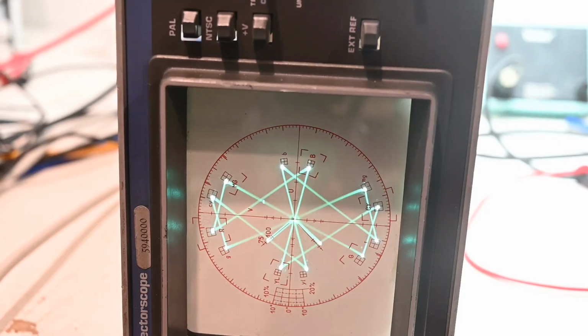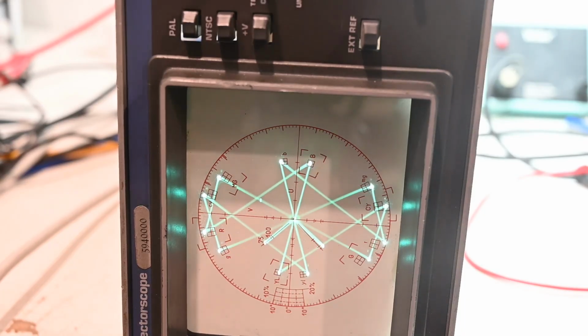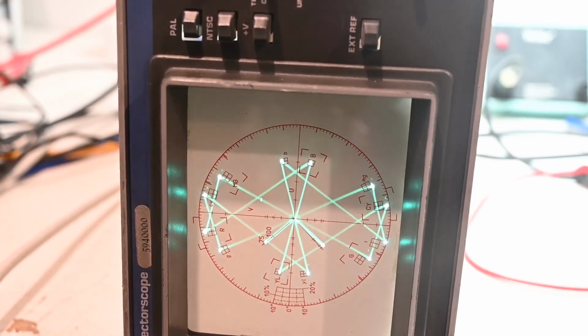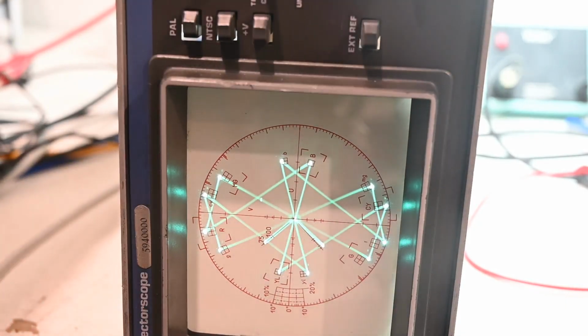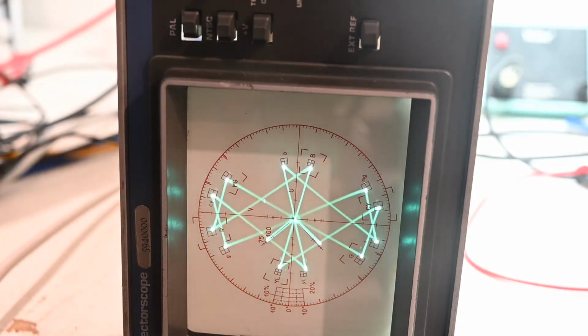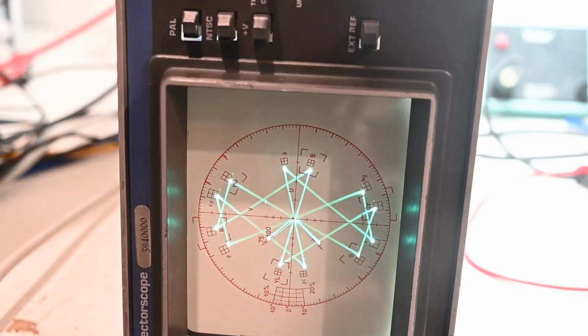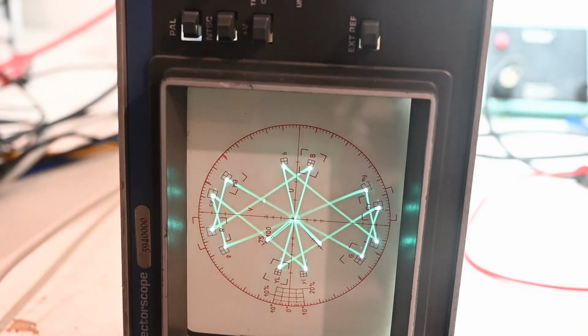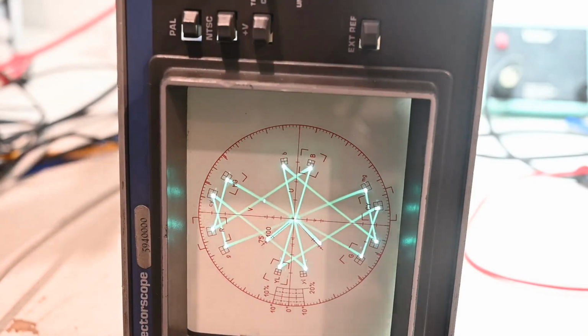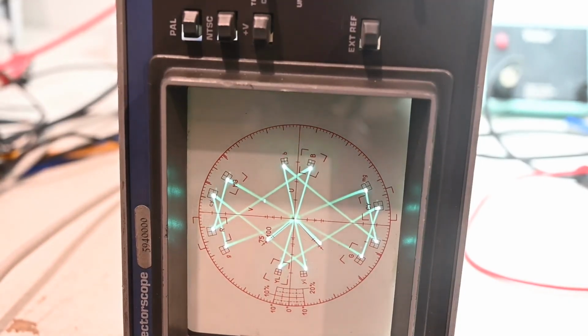So this would imply to me that probably there's another adjustment, maybe in the gain block, which is set incorrectly. So I'm going to shift that to the center, and we'll see if we can find another adjustment in the gain block. Let's try that one there. No, that one doesn't do it. Here we go. So what's that one set? Yeah, so that one was actually a bit off center. So if I bring that one to the center, that's better. So yeah, I don't ever think an adjustment should be at one end of its travel. They generally are designed so that they're in the center and their optimum state. So that looks quite a bit better.